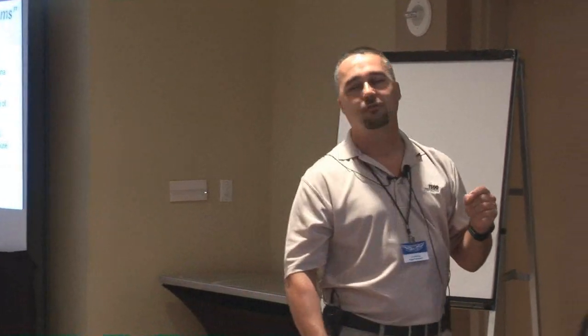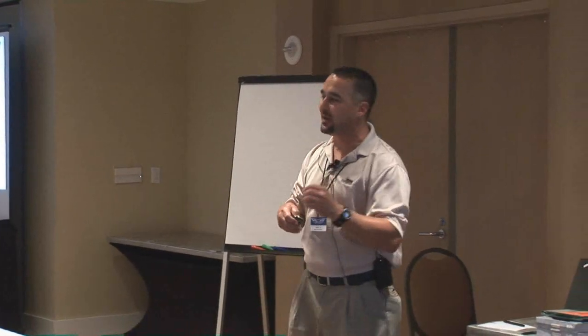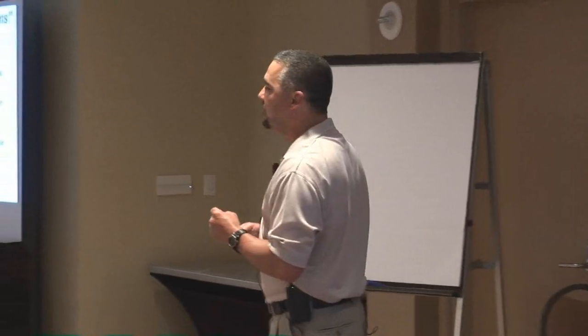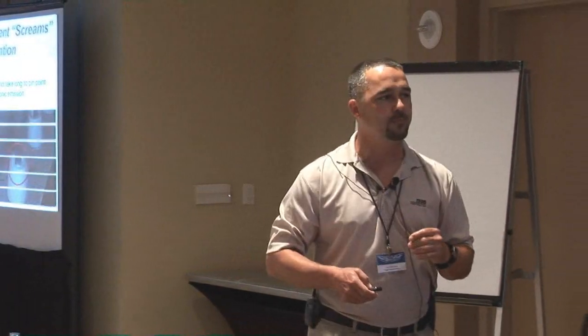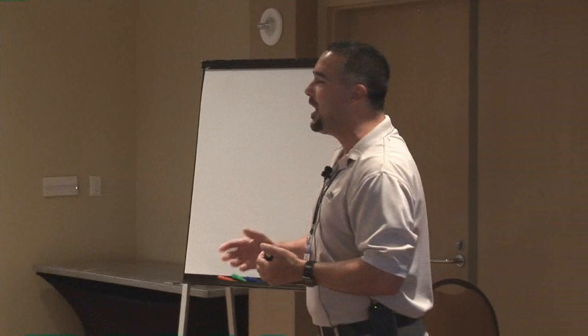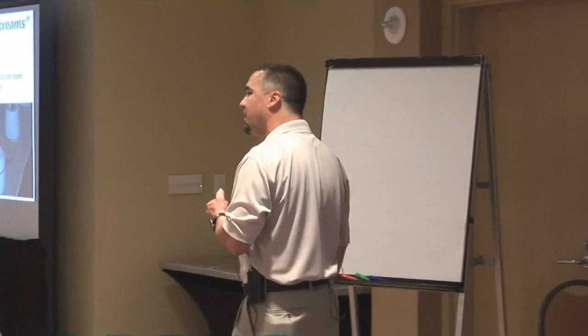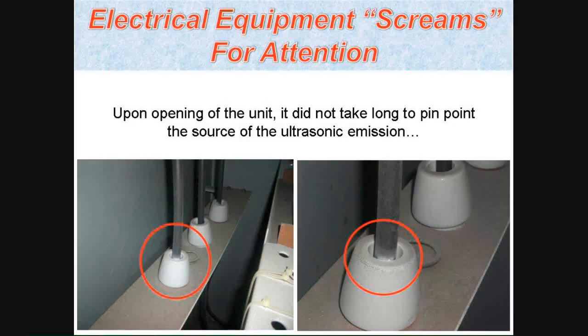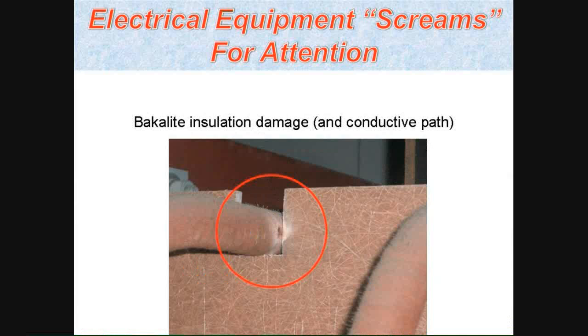But when the nitrates are formed and it breaks down insulators, now over that 360 electrical degrees, you begin to have discharges anywhere on that sine wave. It gets less uniform in nature. When the equipment was opened up, after they had gone back with a planned shutdown and a very tight time window, it was very clear that the analysis was not incorrect. And on the ceramic insulators, you can see the byproducts of destructive corona, the nitrates or white powder that we look for that will ultimately break down that conductor insulation.